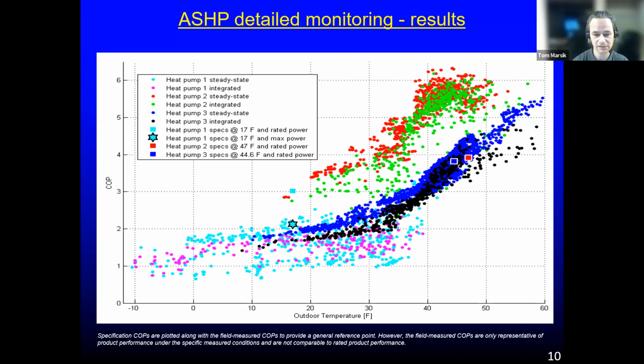And so because of the specific situation in Fairbanks, if you do the numbers, we are looking at a COP of about 2. And it actually applies to both. We are kind of lucky in Fairbanks. It applies to the CO2 emissions, the break-even point, as well as the costs.